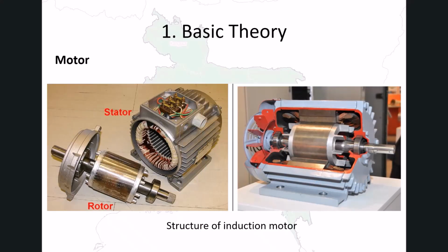Electrical energy is converted into mechanical power by a motor. The motors used in electric facilities are AC types, which are classified into 3 categories: commutator type, synchronous type, and induction type. For pumps and other machinery used in water supply facilities, induction motors are generally the most common.